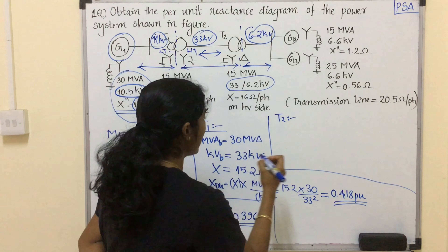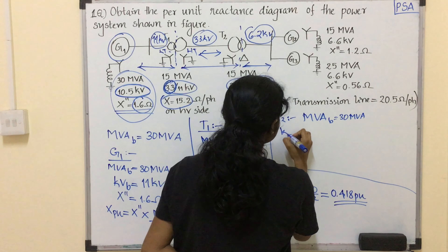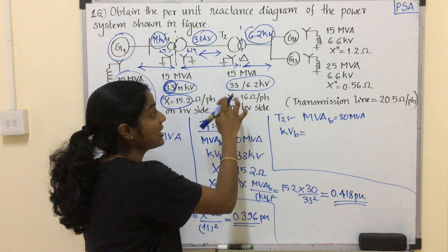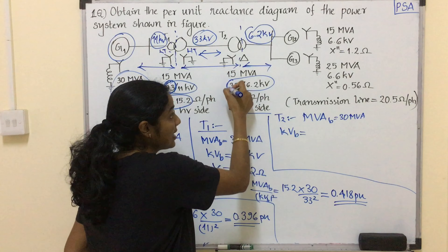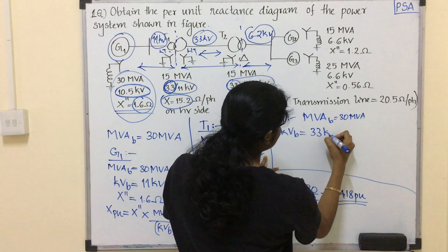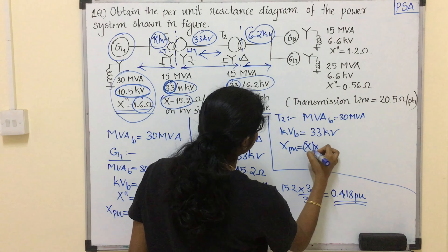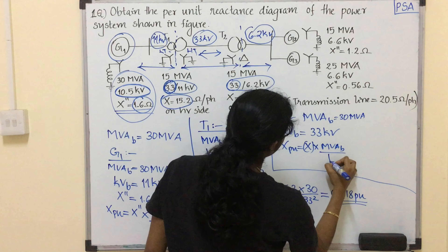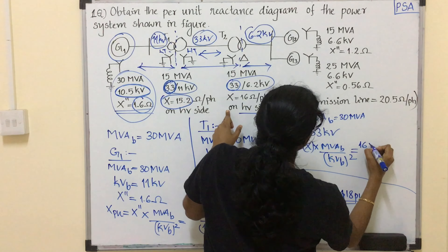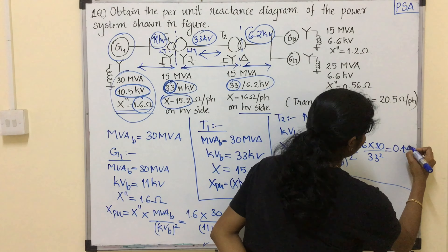For T2, again MVA base equals 30 MVA. The reactance X is equal to 16 ohm per phase on the HV side. HV side value is 33 kV, so KV base equals 33 kV. X per unit equals X multiplied by MVA base divided by KV base squared, which is 16 multiplied by 30 divided by 33 squared. The value will be 0.44 per unit.